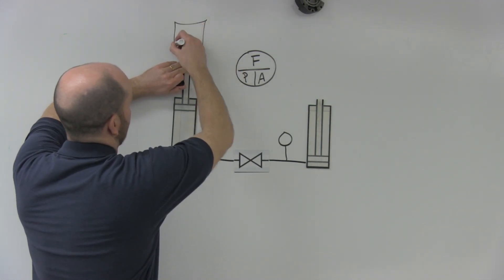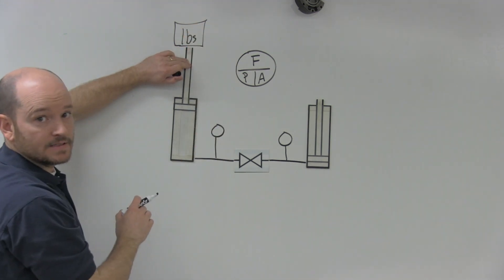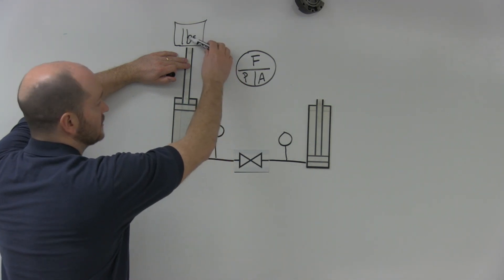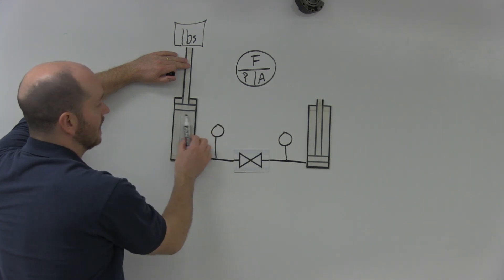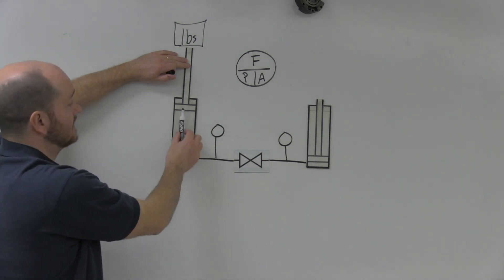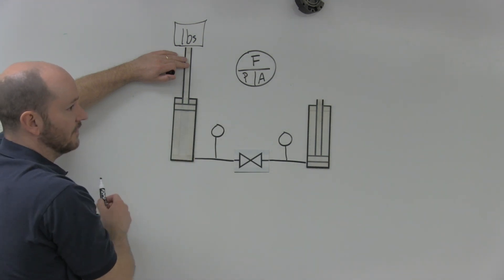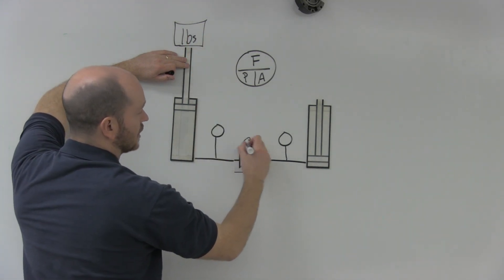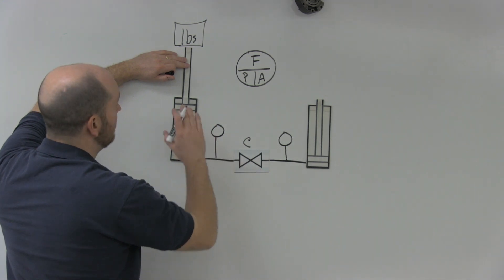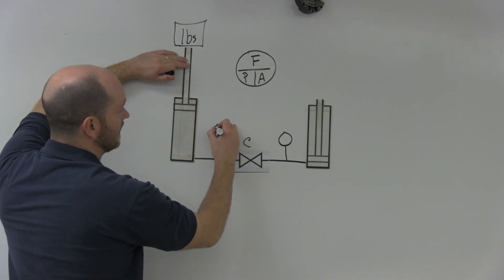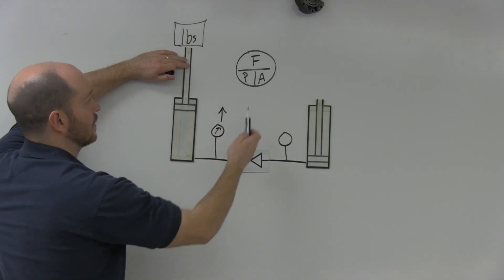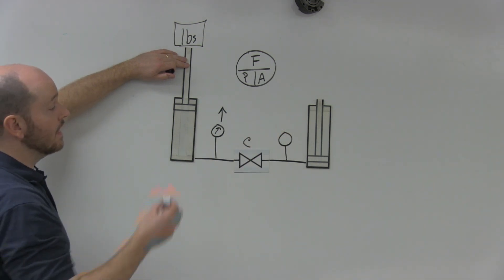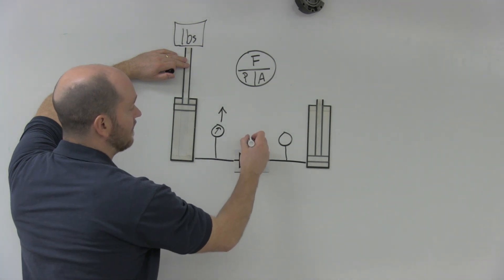With the valve closed, if I put a force on here — some weight — that's going to create pressure. That pressure is going to be based on how much force is being applied and the area through which it's being applied: the bore of the piston, or the square inches of the cylinder. If this valve is closed, there's no flow, this cylinder stays put, and all that happens is pressure goes up.